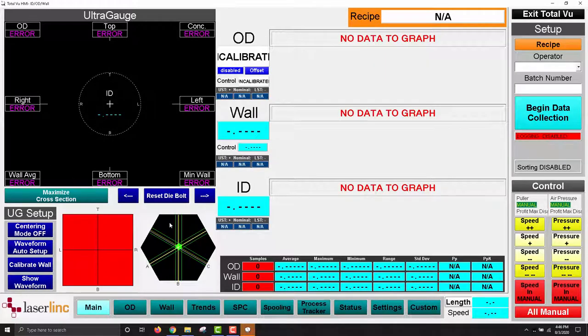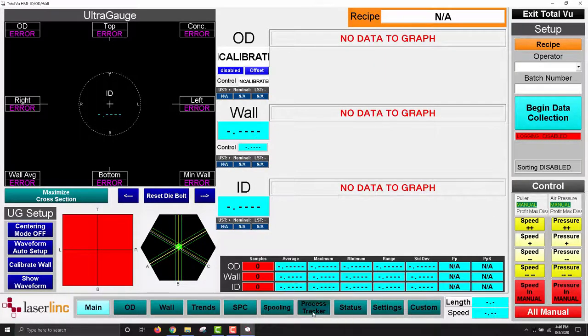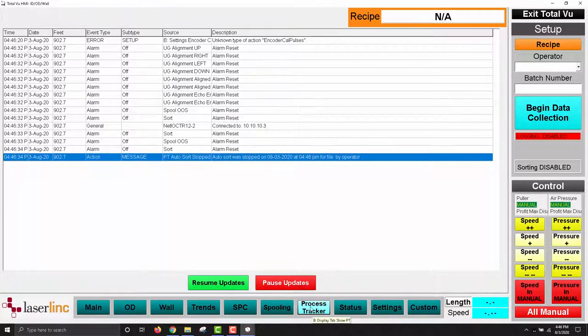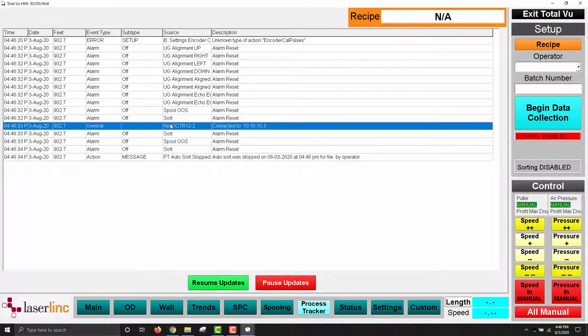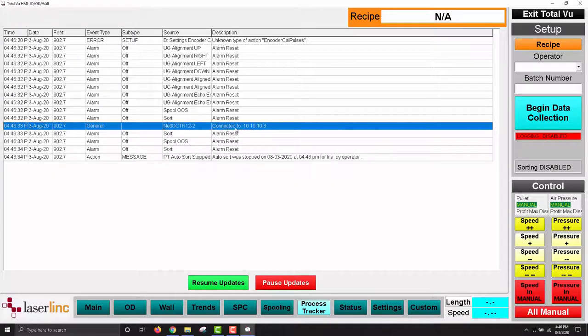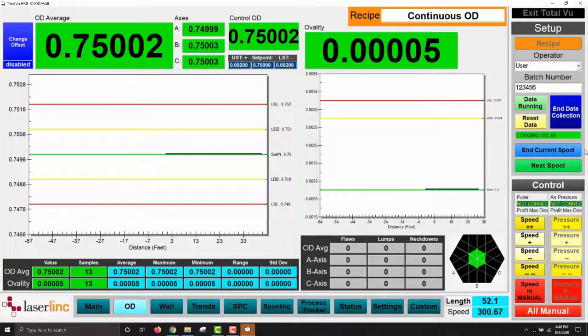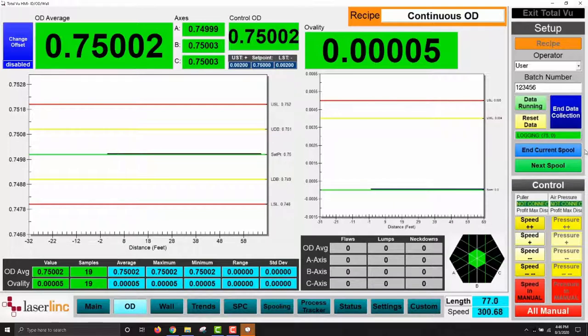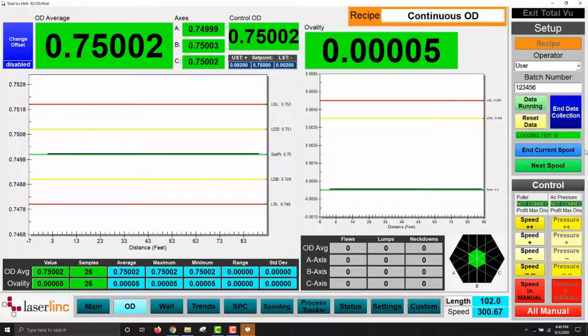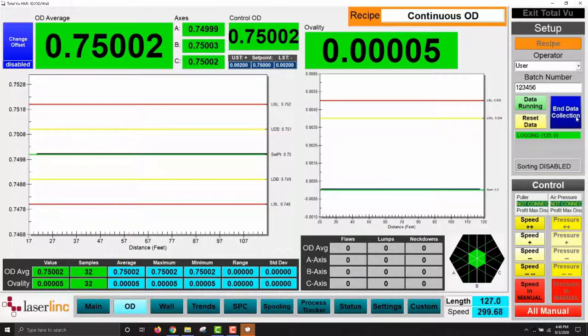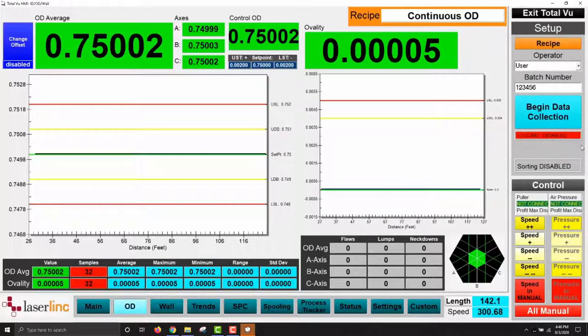To tell that the NetIO is communicating, view the process tracker or error log and look for a message stating the NetIO is connected. We can also perform tests to confirm successful connection by executing actions in TotalView that should translate into relay actuations. For example, if the NetIO is connected to a light stack where the various colors are associated with various alarms in TotalView, we can manually turn on and off the alarms and watch to see that the relays are actuating properly.